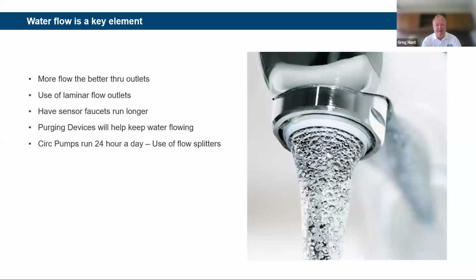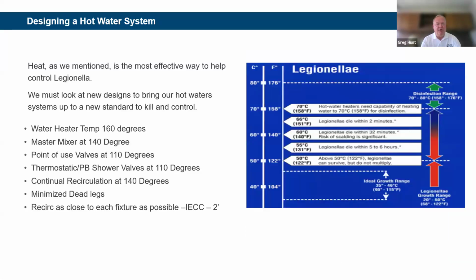Now I know you mentioned water systems, so I want to touch on designing a hot water system. This is an ongoing process, and we deal with this a lot with engineers trying to get an understanding. Going back to when Legionella and where it all started, back in the 70s—it's not that it started in the 70s, it was there, but we were designing plumbing systems that had tempered water running through the entire system at 115 to 120 degrees throughout, which caused the majority of our issues within the plumbing systems, the biofilms, and everything else.